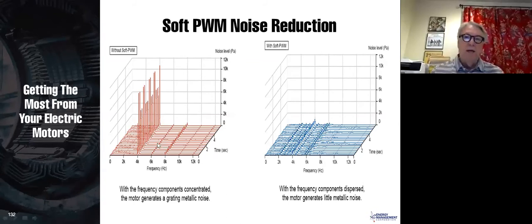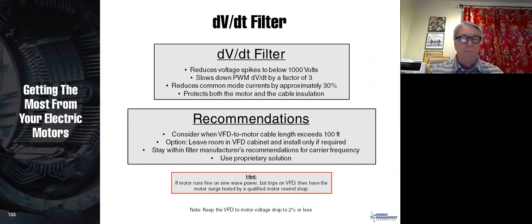The other thing is, because of magnetostriction, whenever you listen to a motor on a VFD, you notice that they sing. They have that little noise that you don't hear across the line. Well, that's the carrier frequency. And if you change the carrier frequency, which you can do on any variable frequency drive, then you will hear that frequency change. With soft PWM, this is without soft PWM on the left, and with soft PWM on the right, you will notice that that noise mostly goes away, and you get a much more complex, pleasing noise rather than that really irritating sine wave kind of noise. So it's another advantage of soft PWM.